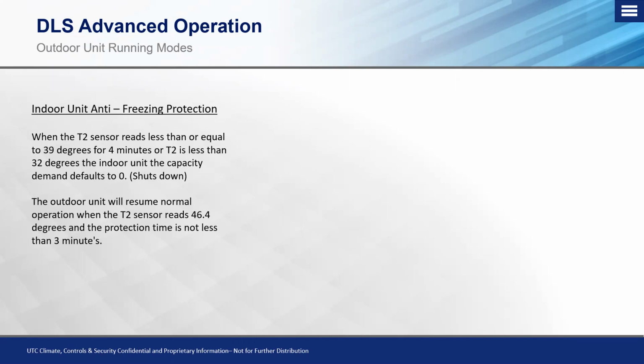However, if it cannot bring up that indoor coil temperature sensor for this example, which would be 39 degrees for a total of 4 minutes, or that sensor is reading less than 32 degrees, we're going to shut the unit down as a safety to prevent any frosting from occurring. And of course, as the frost dethaws, causing any water damage in that space for the homeowner, depending on if it's in the bedroom, the living room, or above something that might be valuable to them.